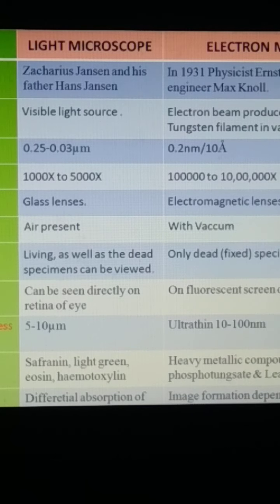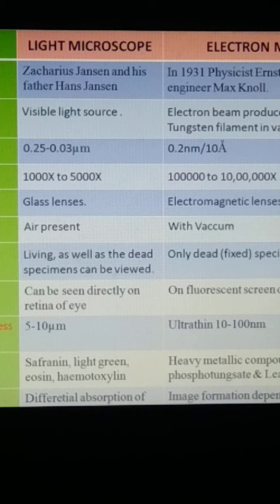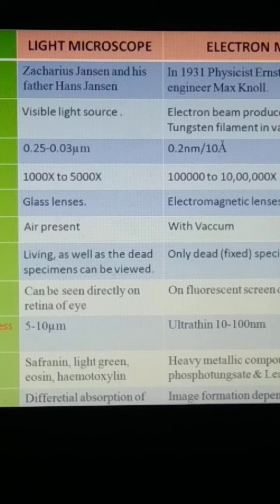Regarding lenses: simple glass lenses are used in light microscopy, but in the case of electron microscopy, we use electromagnetic lenses. Regarding the body tube: in the case of a light microscope, air is filled inside. But in the case of an electron microscope, we have to remove the air and create a vacuum. Otherwise, electrons will collide with each other and a strong, narrow condensed beam cannot be produced. Moreover, this collision can destroy the tungsten filament.